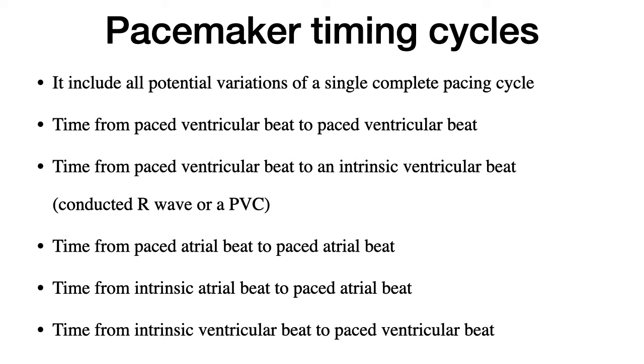The understanding of the various pacing modes and the paced electrocardiograms needs a full understanding of the pacemaker timing cycles, and these cycles include either sensed or paced events and periods when the sensing circuit of the pacemaker is refractory. The knowledge of the relation between the different elements of the paced ECG enhances the understanding of the pacemaker rhythm. Each of the timing circuits of the pacemaker can function in only one of two ways. When a given timer starts, it can proceed until it completes its cycle. This completion results in either the release of a pacemaker stimulus if there is no native rhythm sensed, or the initiation of another timing cycle when sensing a native activity.